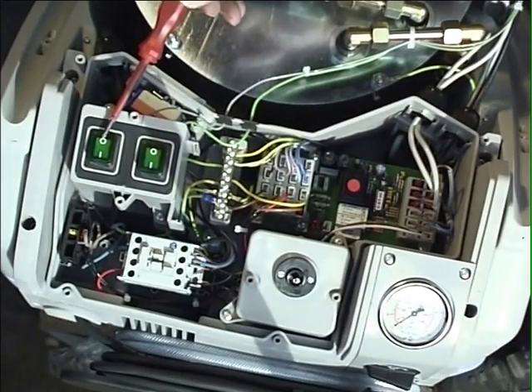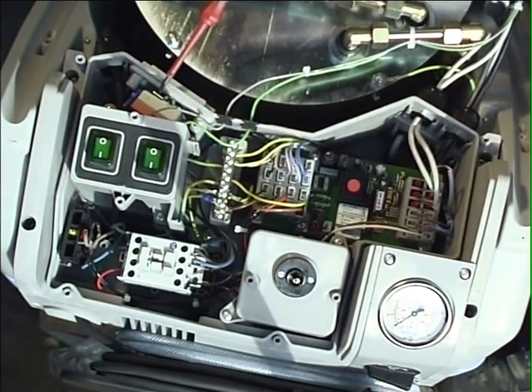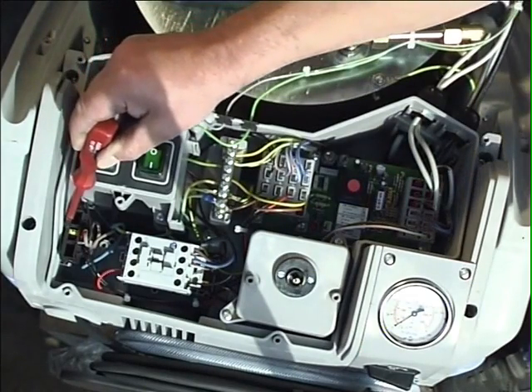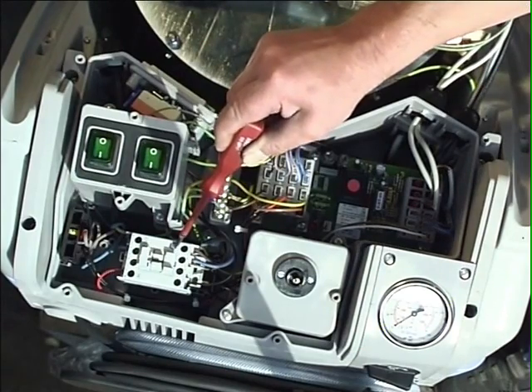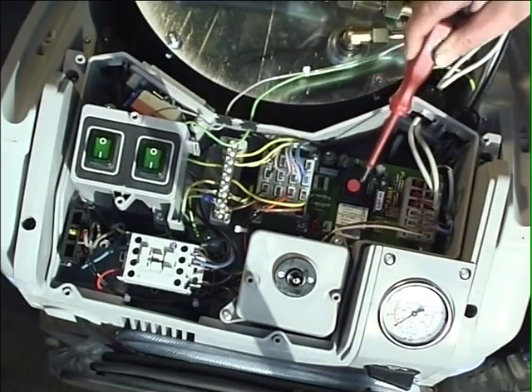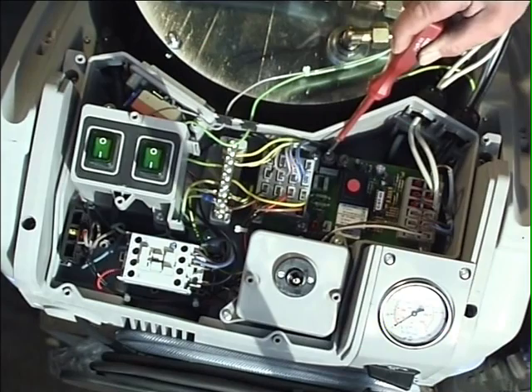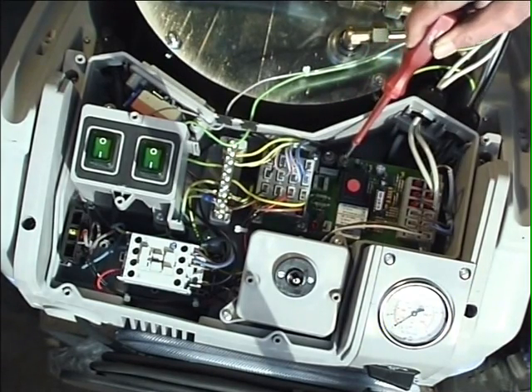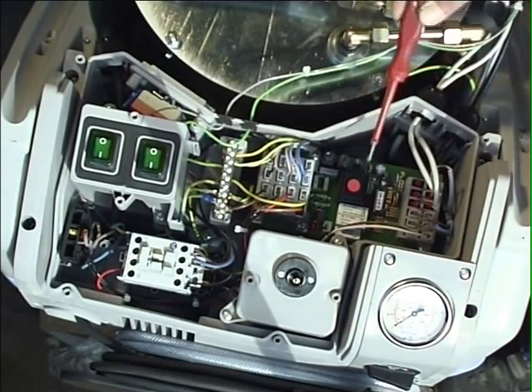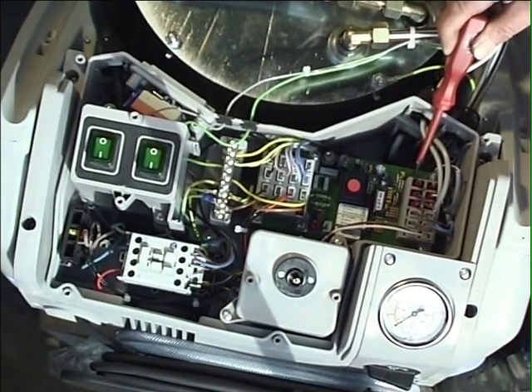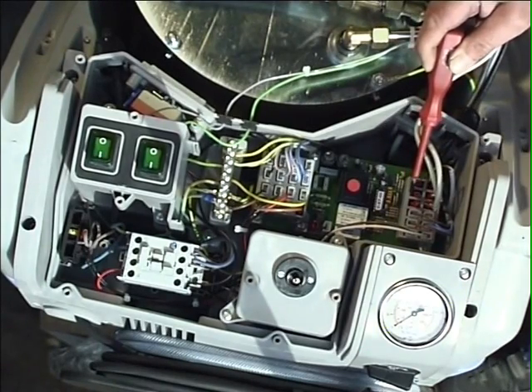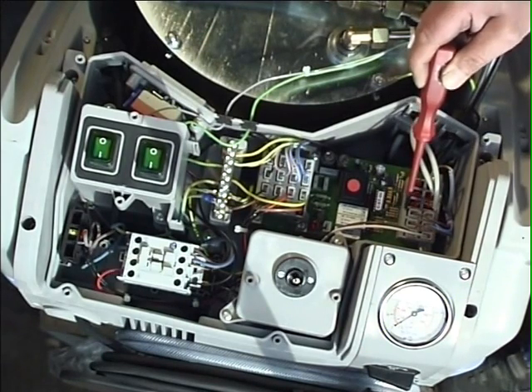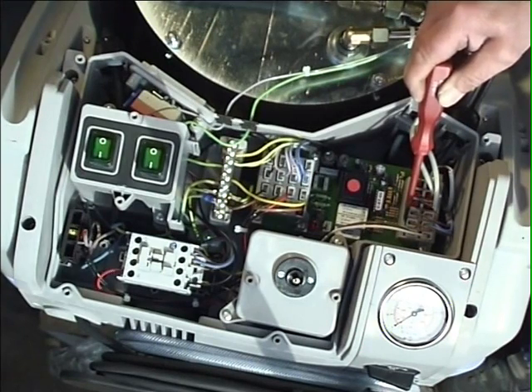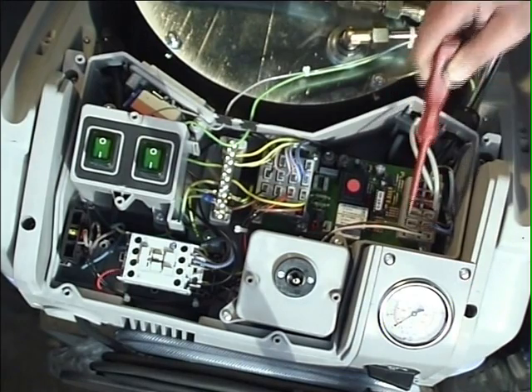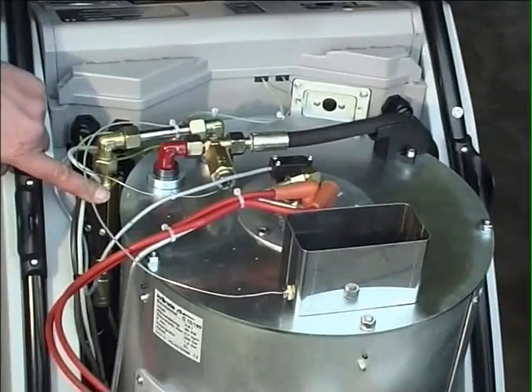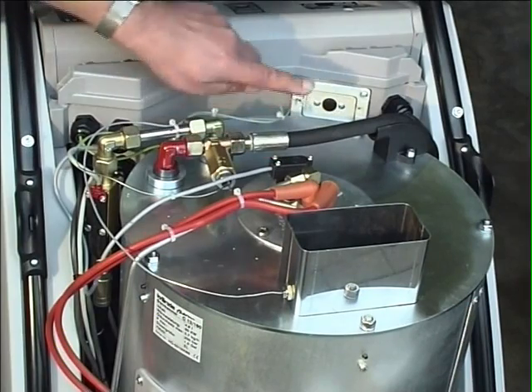Main switch, ignition on-off, excess temperature release, motor protection switch, motor contactor, thermostat, board on which these are found, fuse for ignition transformer left, on the right hand fuse for burner motor. And connections for photocell, float switch, flow monitor, red pressure switch for motor start-stop, black pressure switch for burner start-stop, and rotation thermostat. Here you will find the flow monitor, photocell and waste gas excess temperature release.